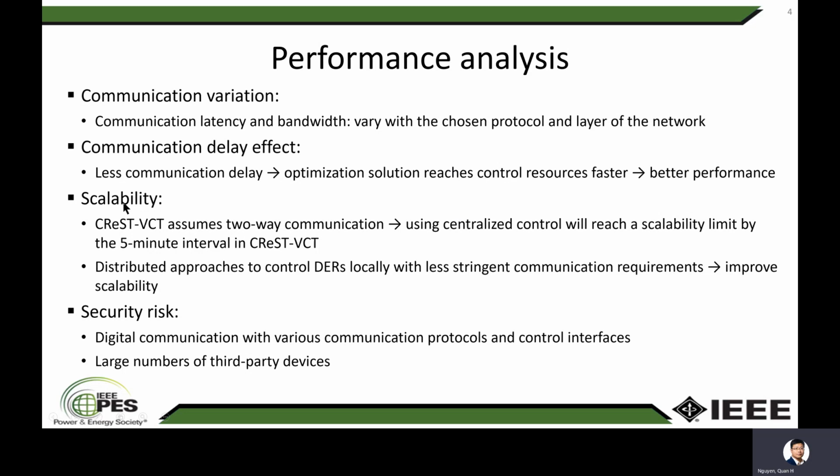Regarding scalability of CReST-VCT, because CReST-VCT assumes two-way communications between EMS and DMS, if we use a centralized control, then it will reach a scalability limit by the 5-minute interval of CReST-VCT operation. Because of that, we suggest distribution operators adopt distributed control approaches to control DER locally with less communication requirements to improve the scalability of CReST-VCT.